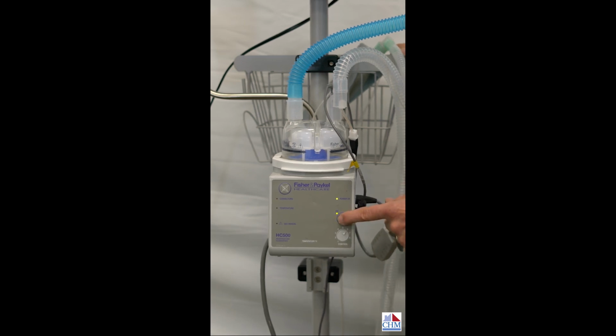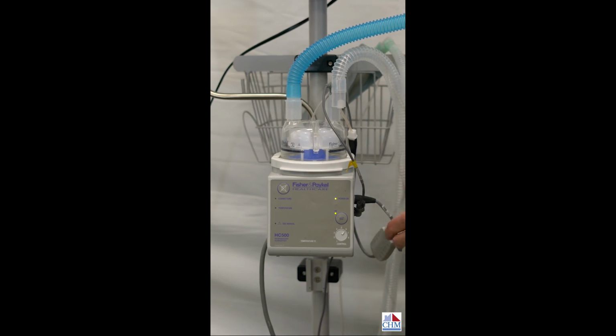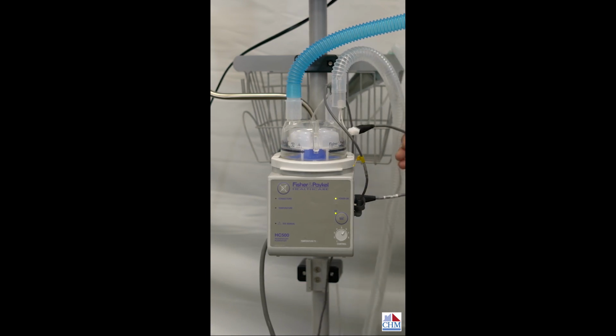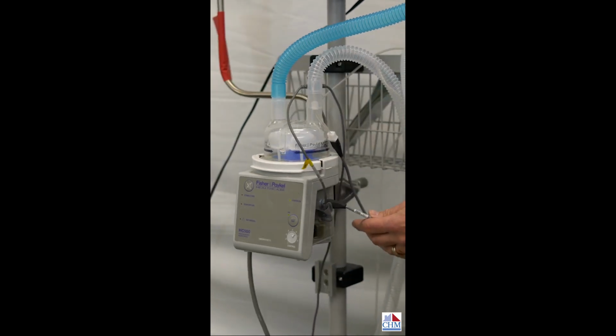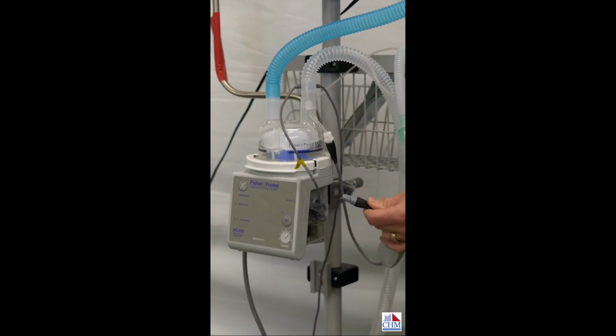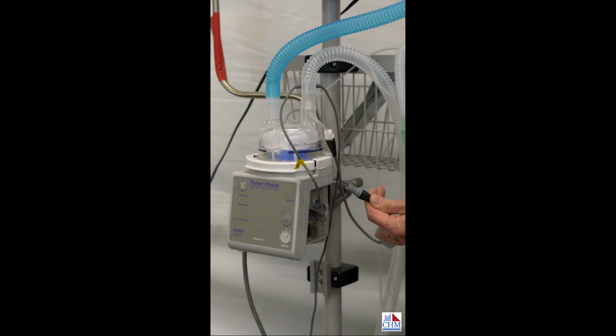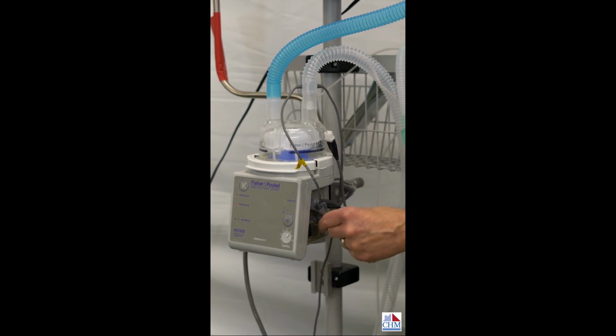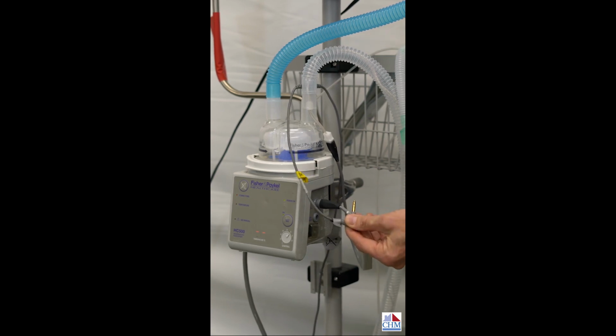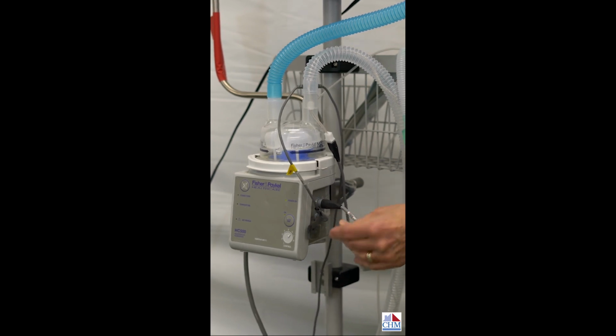So always check that first, because that's the easiest thing to connect or correct, and the easiest thing to accidentally hit to turn off. The other things that could happen are either the temperature probe or the heated wire. All right. So these are connected on the side also, and you can see if either one of these are disconnected, here's the heated wire adapter, or the temperature probe, either one of them are going to give us alarms. And that's pretty obvious that they're disconnected.